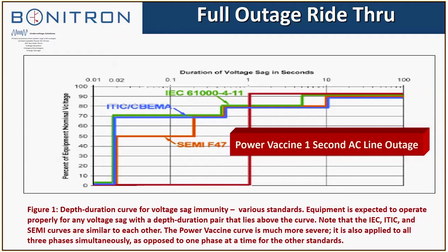Now we're moving on to short-term full outage ride-through, and the first thing I wanted to put up was the spec that actually motivated us to use the Ultracap energy storage, which is the 1-second power vaccine that you're going to see with the Samsung fabs. Don't need to go into too much detail with that. But now when we're talking about full outage ride-through, we're taking the ride-through voltage regulator booster and adding the components, the modules, and the energy storage that goes with it.